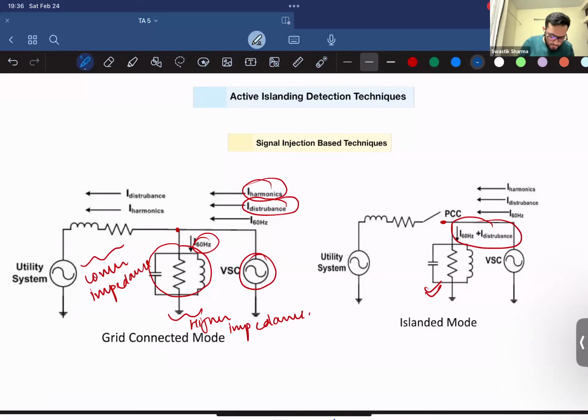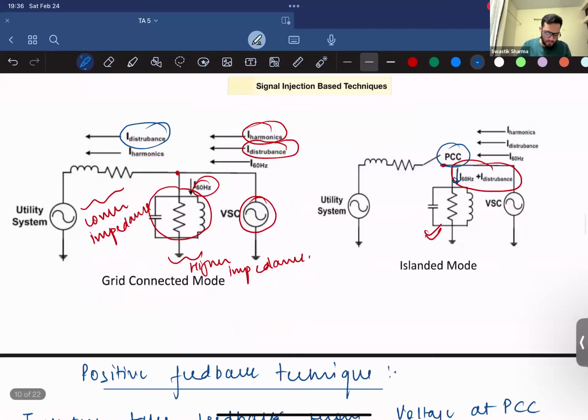It's just that the disturbance was being passed on to the grid side load if the PCC was connected. While the PCC was not there, it was being passed on to the microgrid side load. But the microgrid side converter was not experiencing any deliberate unstable operation.